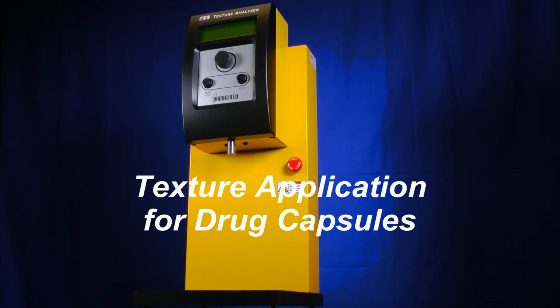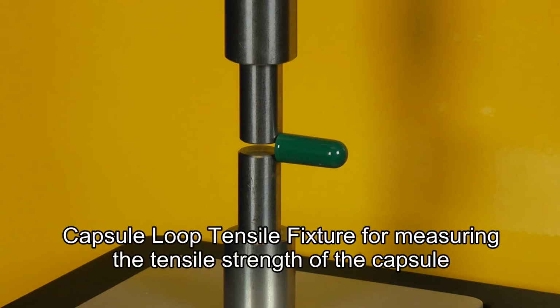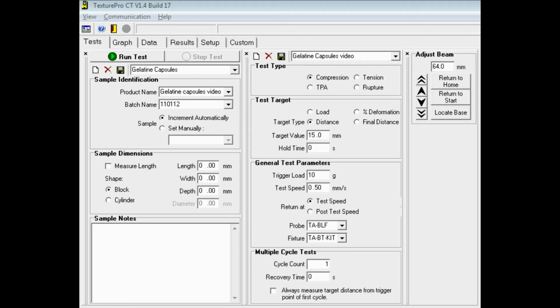This is a tensile test for drug capsules using the CT3 texture analyzer. Here we see the capsule loop tensile fixture for measuring the tensile strength of the capsule. This test will be performed using the Texture Pro CT software.